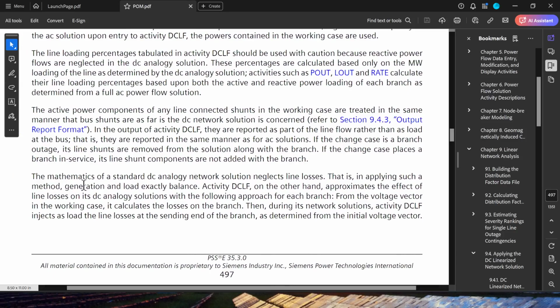Yeah, so here you can see that in general, the mathematics of the standard DC load flow ignores line losses. Therefore, when you do the load flow, the solution you get will be such that the generation and load are exactly balanced. However, in this PSSE DC load flow, when you select the option to model the line losses, it takes the initial voltage solution that you currently have, calculates the losses on the branch, and then models it as a load on the sending end of the branch.